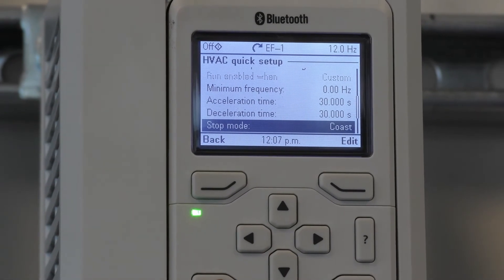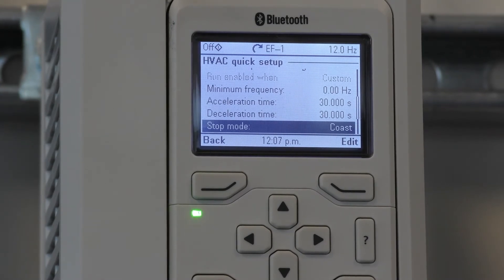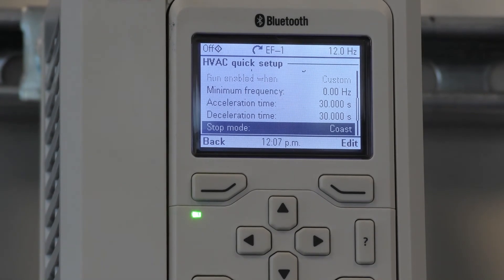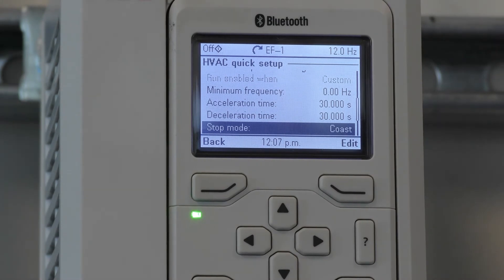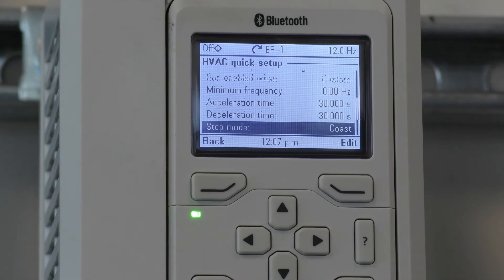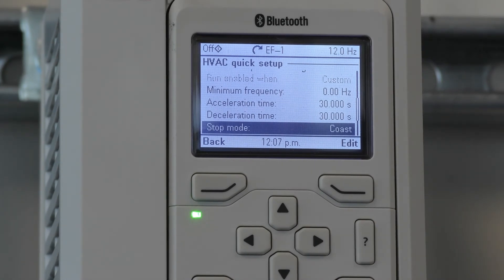Stop mode is utilized to edit between coast and ramp. If you're utilizing coast, the drive, when it receives a stop signal, allows the motor to freewheel until it stops. If you're using ramp, the drive slows the motor down according to the deceleration time. Ramp is sometimes used in pump applications that utilize a check valve to keep the check valve from slamming.